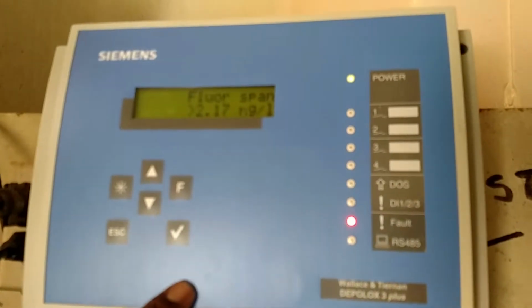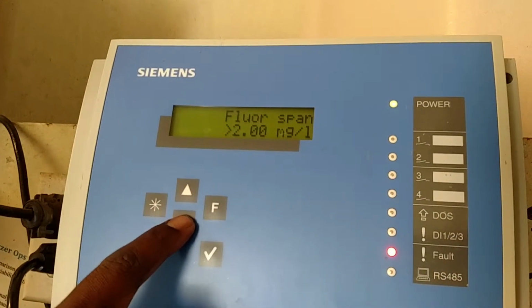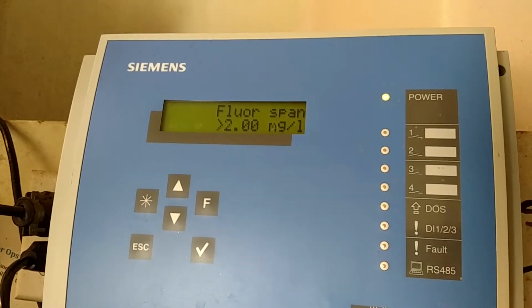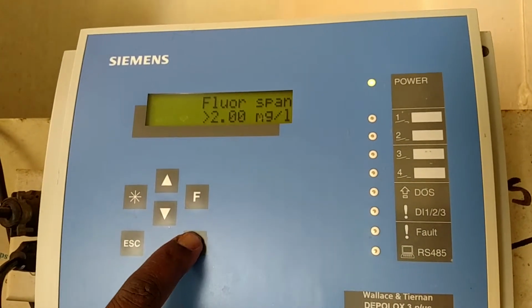So now that appears to be somewhat stable. So my reading is going to be a 2.17. So I come here, click on that to calibrate it. I'm going to check mark to calibrate, go into calibration mode. Then I just take it to 2.0 and hit it again.